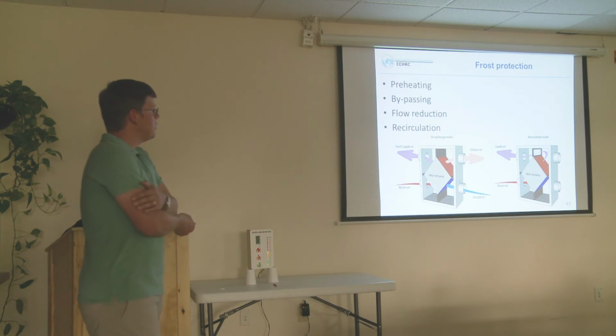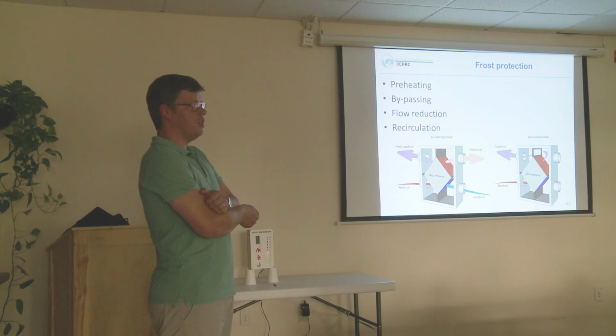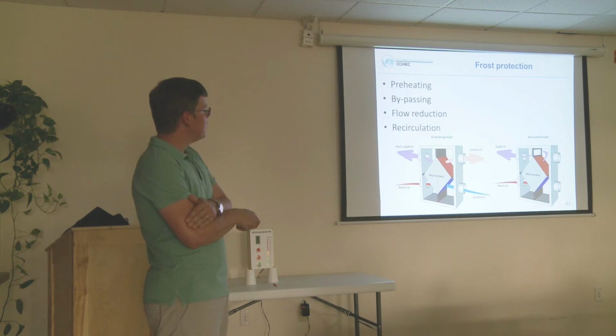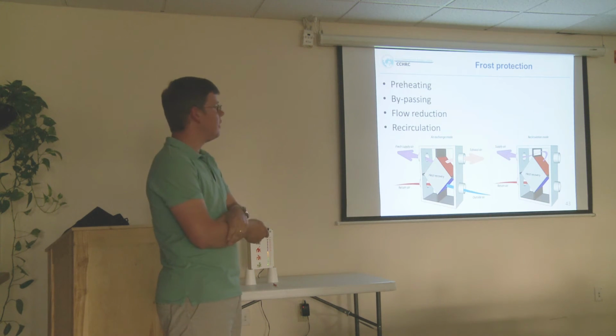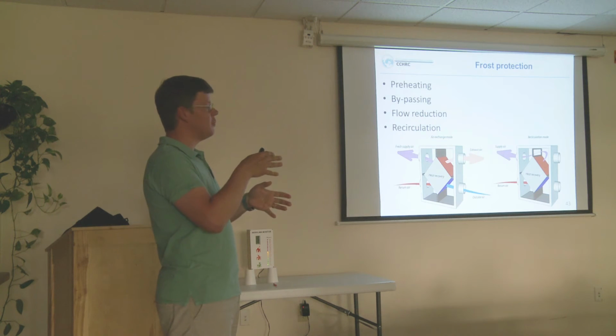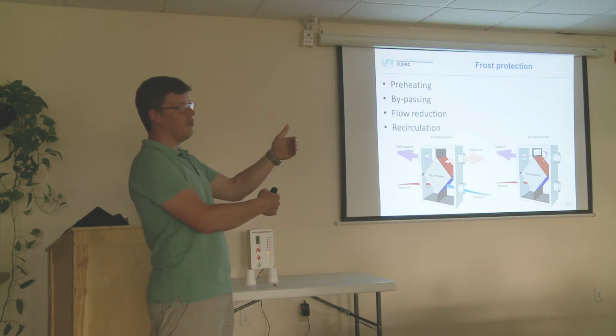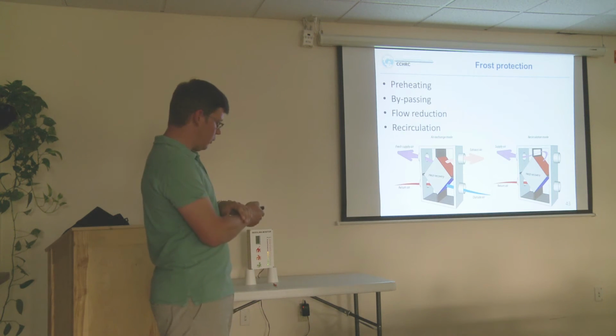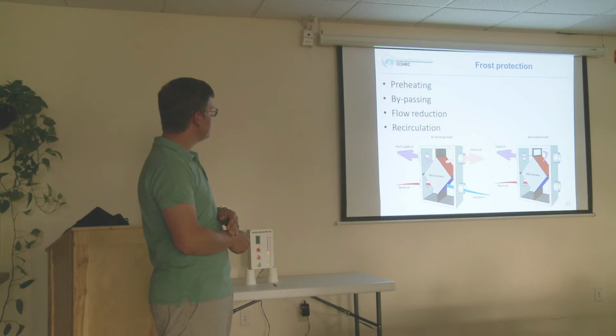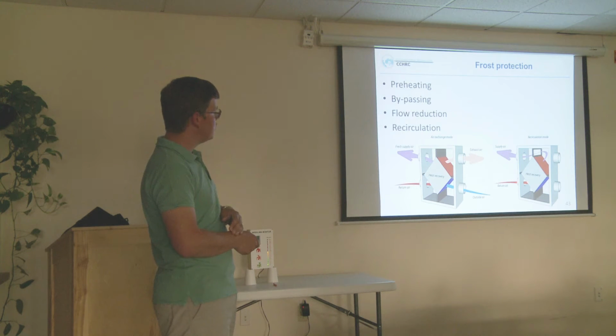Another strategy is recirculation. That is a strategy very common here in Alaska. Most of the units which are sold here have this one, and basically if the temperature outside drops below a certain level, then the unit rearranges some dampers, so it closes to the outdoor environment and just circulates the inside air. We can see it here in the picture. Under normal operation, the return air from the house goes to the unit, then goes through a heat exchanger and goes out of the house. The fresh air comes in, gets preheated, and goes to the house. When the recirculation is active, the return air comes to the unit, goes through the heat recovery, gets cooled down a little bit because it's heating the heat recovery with all the ice in, and then through this hole goes back to the house.